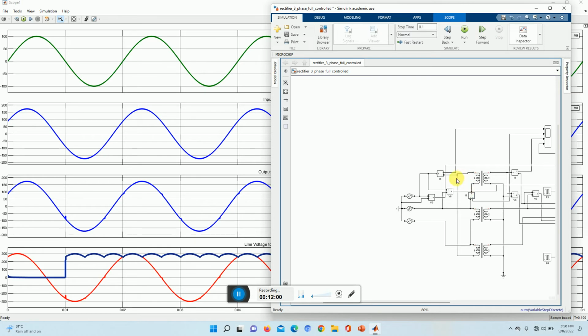The input is delta connected, so between any two windings we have the R phase terminal giving 173 volts peak. On the secondary side, since it's a 1:1 transformer, we also get 173 volts output. Apart from that we can measure the phase voltage and the line voltage on the output. The phase voltage is measured between terminal 1 and the neutral terminal; since it is star connected, this phase output voltage equals the winding phase voltage, 173 peak, and the line voltage will be root 3 times that, about 300 volts.